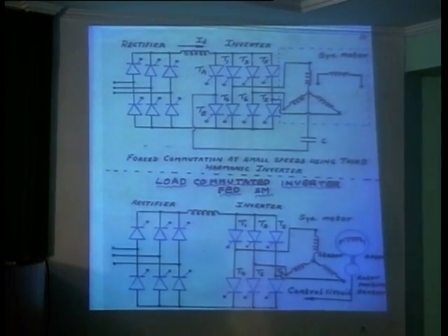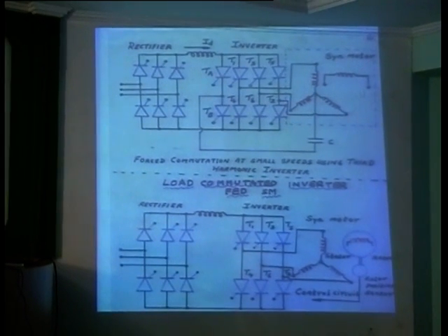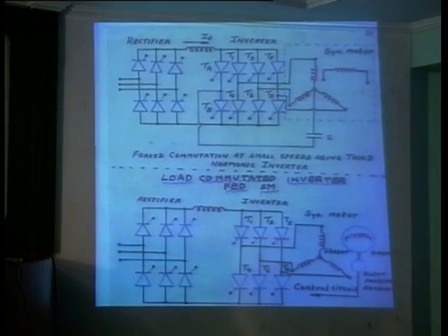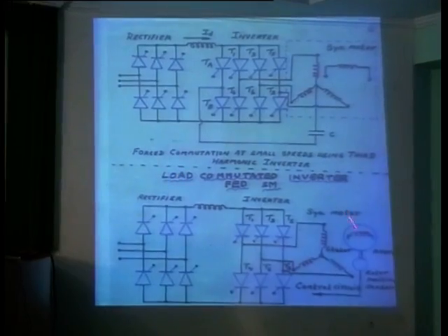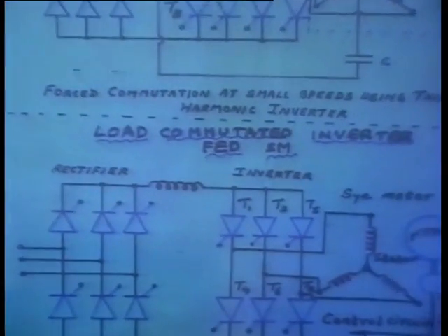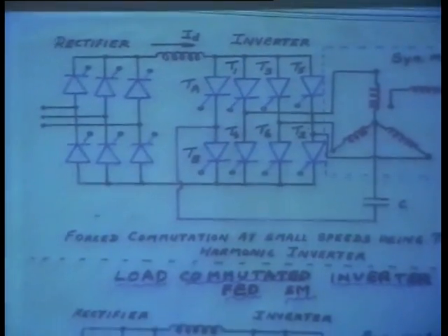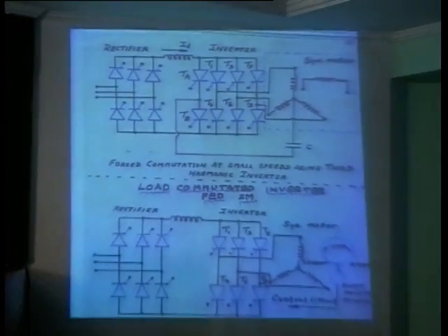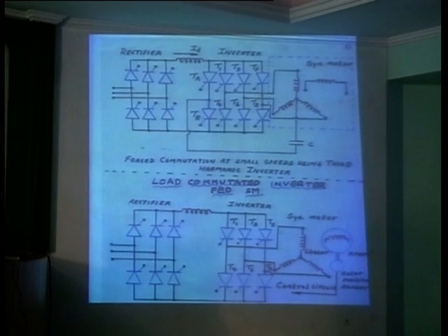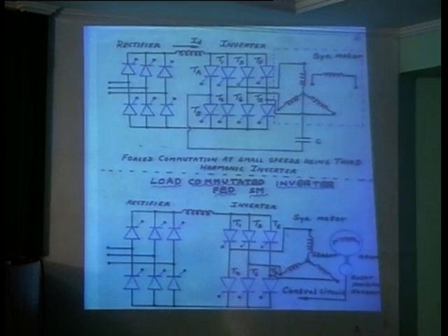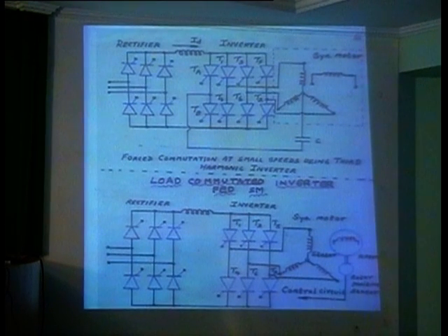So the advantage of a synchronous motor: if you have an over-excited synchronous motor, it operates at leading power factor. You don't need forced commutation. Only lagging power factor circuits require forced commutation. Leading power factor circuits don't require forced commutation. What is commutation? The process of turning off the SCR is called commutation.